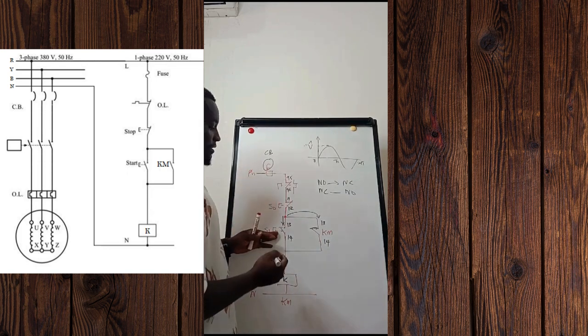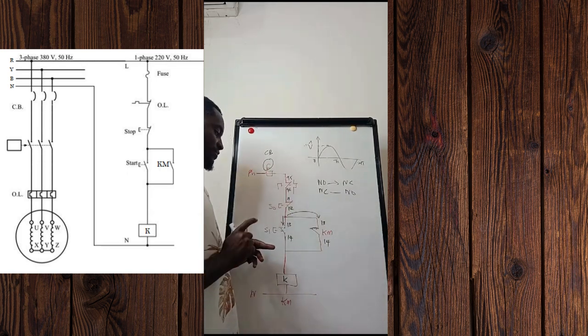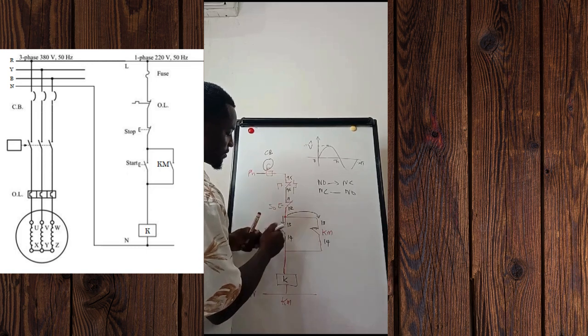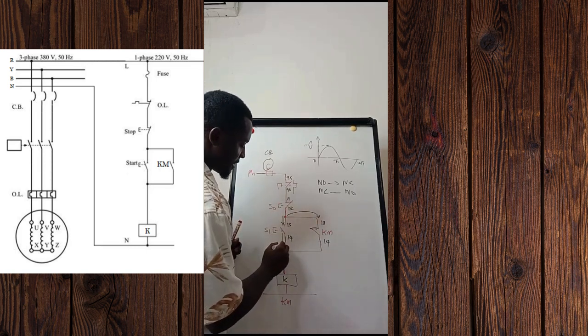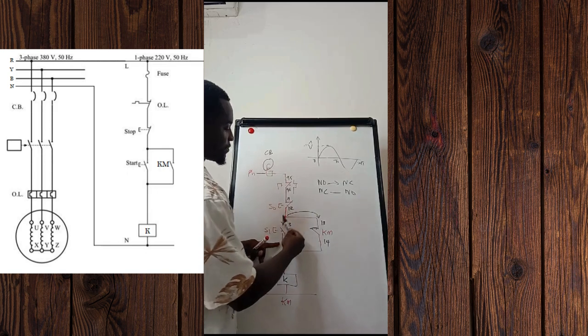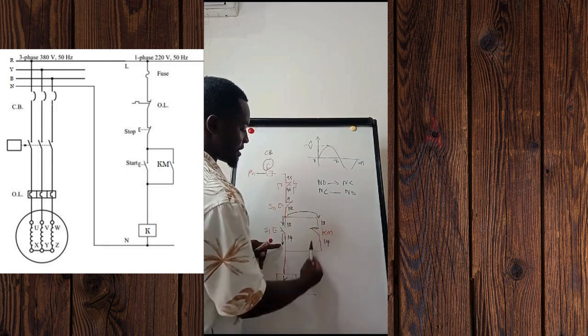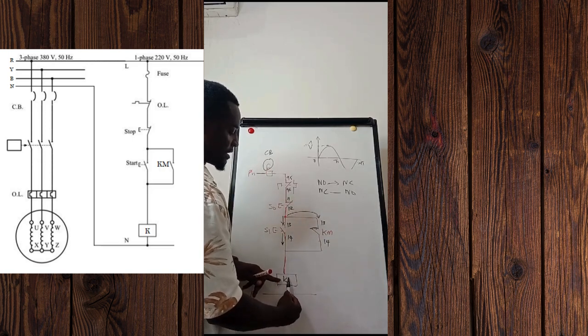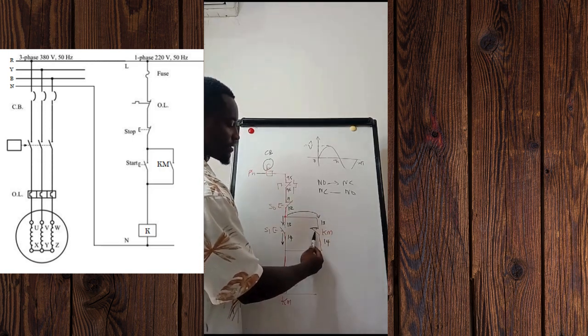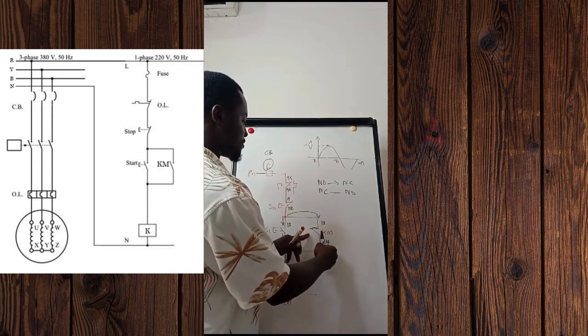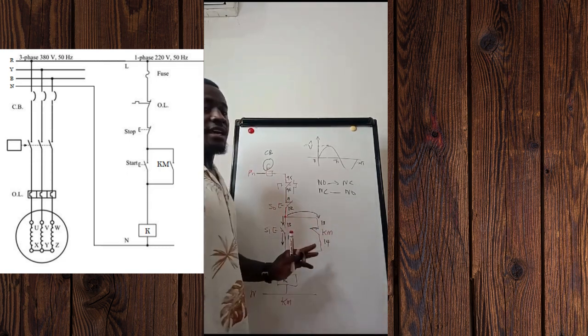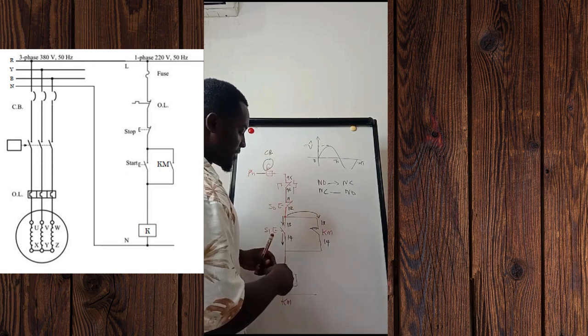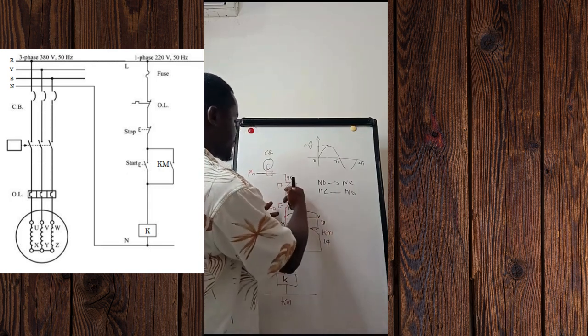Since this is a push button, once you press and release your hand, it retracts back. Once it retracts, that contact returns to open and current cannot flow through it anymore. However, since the coil was already energized, the auxiliary contact has closed, and current now keeps moving through it to keep the coil continuously energized. This is what some books and lecturers call a hold-on contact — it holds the coil to keep it energized, allowing current to keep flowing from the upstream.